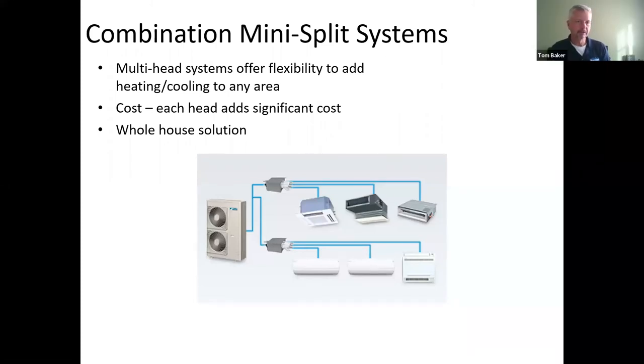Okay, absolutely. And this is a good segue into something I haven't mentioned yet, but should. With the heat pump, you have 2 options. You need an indoor unit with a fan to run the heat pump. And in most cases, that would be an electric air handler or an electric furnace, which is called an air handler. It has a coil built into it. But in the Northwest, it's also very popular to use a gas furnace to run the air handling capabilities. So you could replace your gas furnace with another gas furnace and then replace your air conditioning unit with a heat pump, and you'd get the benefit of energy savings through our 6 or 7 month winter heating system. And it would, in the long run, pay off in energy savings very well. And if you've gotten over 20 years out of your air conditioner, you're an example of somebody who probably took care of it and maintained it and enjoyed the reliability of those systems.